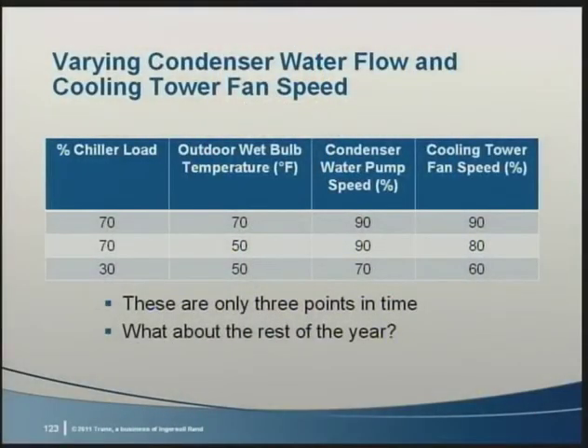consumption. Now the chart here shows the three operating points we just covered, but there are a lot more loads at various wet bulb temperatures. How do we control the system at all those conditions? In a job featured in the ASHRAE Journal in June of 2006, control of a chiller, pump VSD and cooling tower fan VSD was discussed.